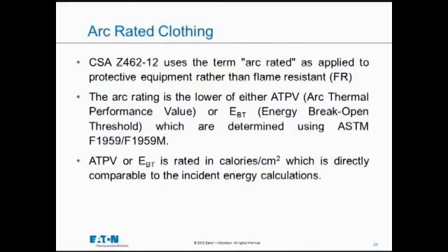That's arc-rated. And arc-rated clothing is tested under arc conditions to see how much is its protective value. And in the middle paragraph is the term ATPV, which stands for Arc Thermal Performance Value. That's the one that we generally see on the labels of arc-rated clothing. So that must match what's on the label, or exceed.